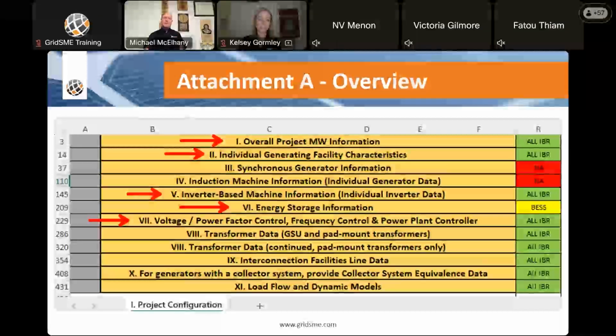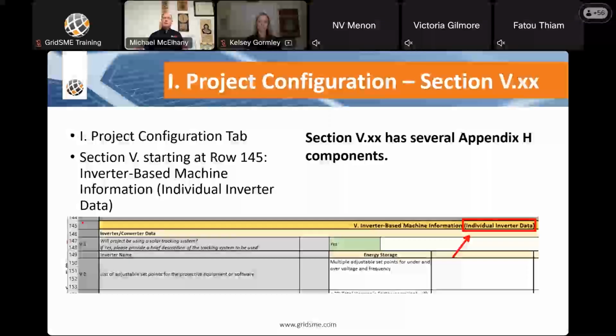I'm going to be focusing on section 5, section V, because that's where we see most of the bucket 3 issues. First thing off the top, it's very important that everyone be aware that section V applies to individual inverter data. We've had projects that we had to kick back because they came in with values that were representative of the entire plant, 43 inverters, and so we see an MVA or other ratings that are well beyond an individual inverter themselves. As you get into the questions, you can lose that fact because it might be a question that, oh, they're asking for this, and so you answer in a particular way. We have to make sure that this is strictly to the capability and settings associated with the individual inverters themselves.